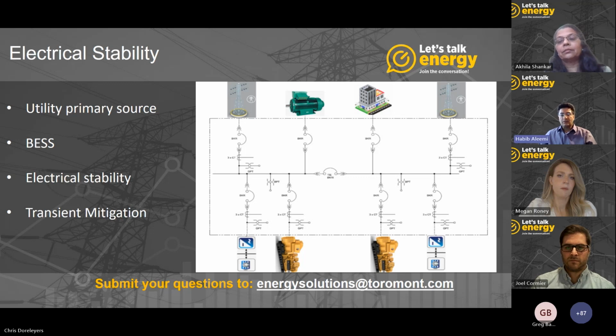For big step loads and electrical stability, the battery bank could be used to take the load swing. And in previous slides, Akhila showed that the recovery response of gas generators is much better when a battery bank is used in the system. The battery bank could be charged when utility is available or there is less load on the gas generators. In this application, we can see that the battery bank could be used for electrical stability. These were the 3 slides I wanted to present.